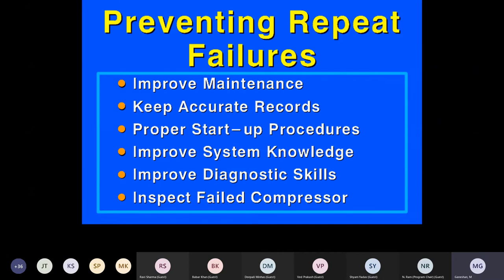The same thing: improving the diagnostic skills. Immediately you have to eliminate: it is not this cause, okay, then it is another, it is not this, then another. So immediately find the probable cause, then you should go to the real root cause before it goes into the failure mode. Whenever something unfortunately fails, then we need to really inspect the compressor, and that can give us some result. Based on that, if we take corrective action, then repeat failures can be prevented.